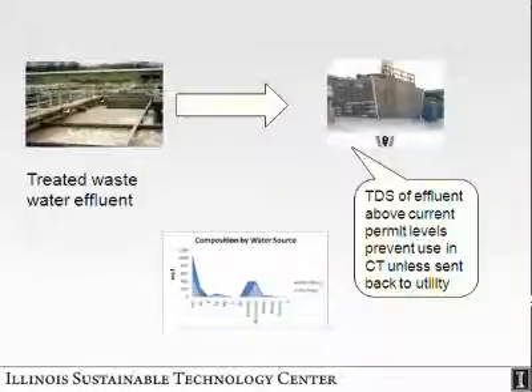The problem here is another regulatory hurdle: this particular ethanol facility is permitted through its NPDES permit to only discharge water from this cooling tower at about 1,000 ppm TDS, total dissolved solids, to a holding point within the site. It turns out the water coming from the effluent treatment plant is about 1,200 to 1,300 ppm to begin with, so you can't just cycle it through the tower into the holding plant. You'd actually have to build a pipeline from this plant to this plant, and then back from this tower to this plant.